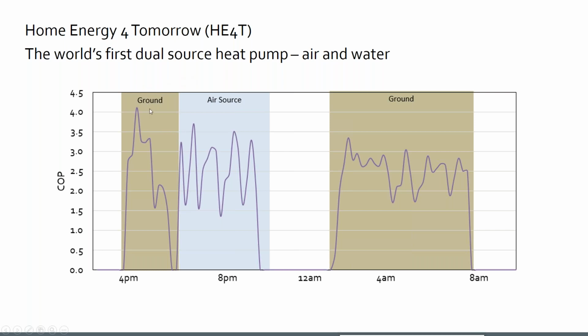And what it basically lets you do is pull heat from the ground source, which will give you a higher COP, until the ground heat sink gets depleted. Then it switches over to air source until the ground recharges, and then switches back to the ground. So it basically allows you to choose between the two heat sinks based on whatever gives you the best COP at a given moment. It's a really interesting approach.